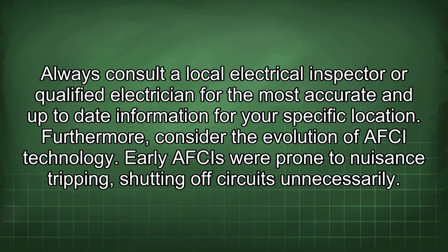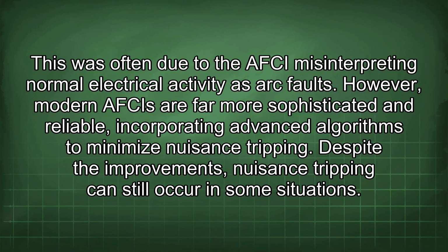Furthermore, consider the evolution of AFCI technology. Early AFCIs were prone to nuisance tripping, shutting off circuits unnecessarily. This was often due to the AFCI misinterpreting normal electrical activity as arc faults. However, modern AFCIs are far more sophisticated and reliable, incorporating advanced algorithms to minimize nuisance tripping. Despite the improvements, nuisance tripping can still occur in some situations.